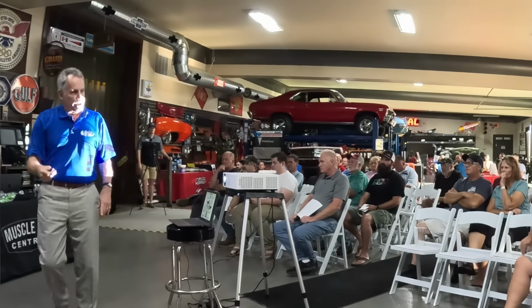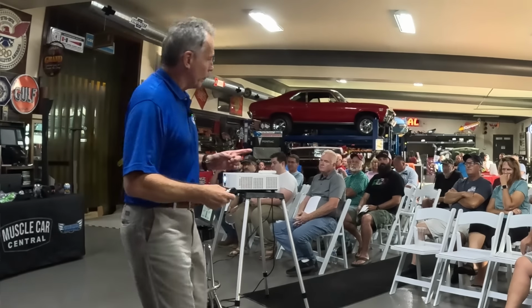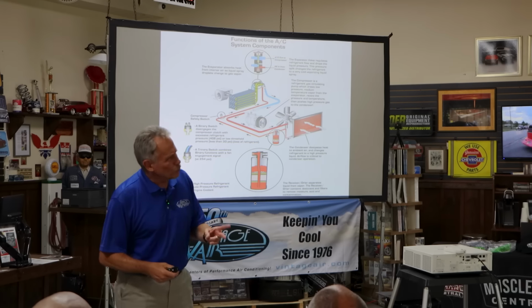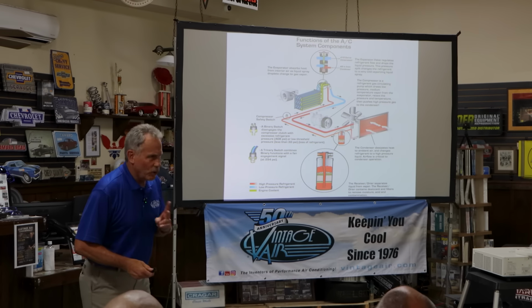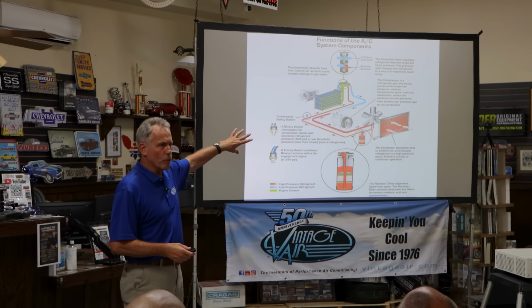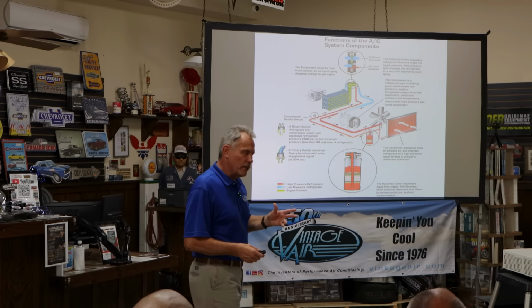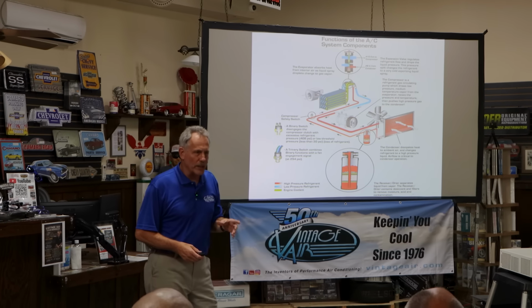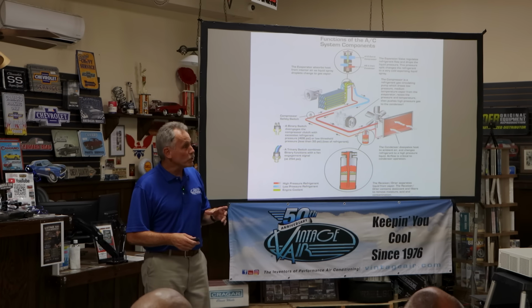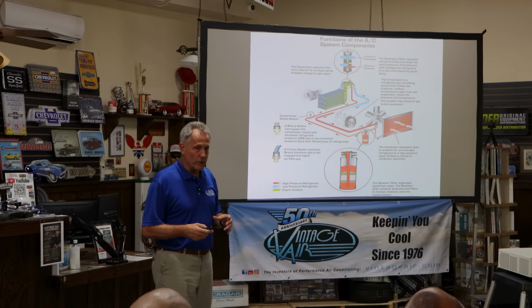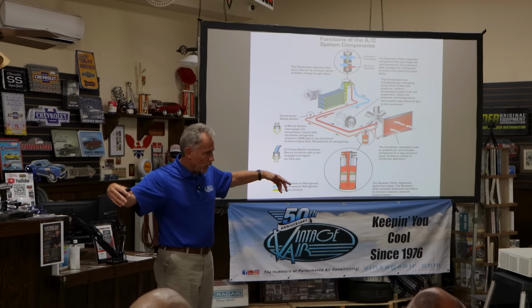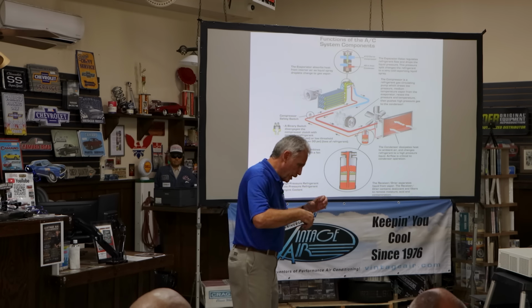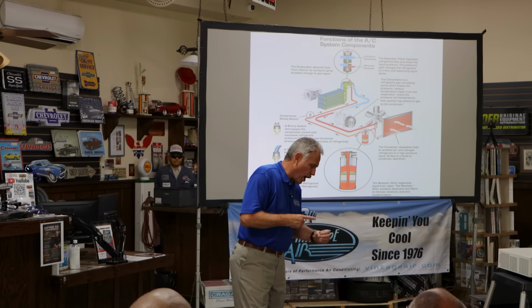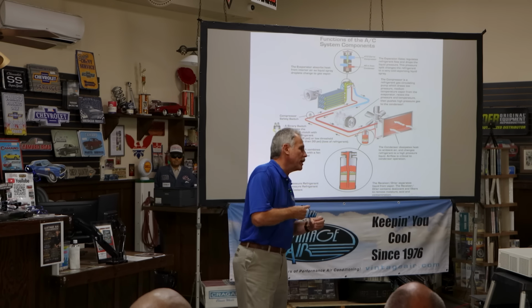One of the biggest differences between 134A refrigerant and R12 refrigerant, I don't dwell much on this anymore because R12 is so far removed from what we normally do now, is that the molecules of R12 were much, much bigger than the molecules of 134A. So when you were charging, looking at that little sight glass in the top of the dryer, you'd keep putting in refrigerant until the bubbles went away.